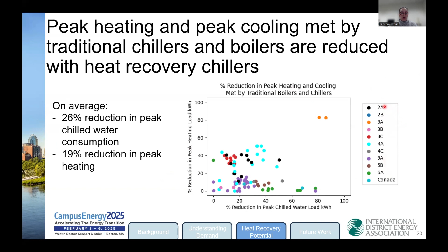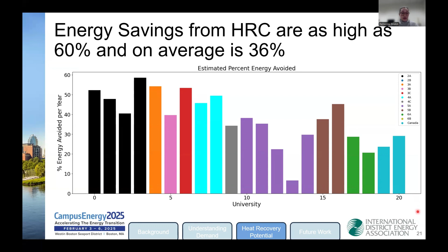Here we can see, with a back of the envelope calculation, what the energy savings from a heat recovery chiller might be for all the different universities. They are as high as 60% and on average about 36%. This is assuming back of the envelope calculations with efficiencies for traditional chillers as well as boilers, and then an electric heat recovery chiller. You can see that the energy savings are possible across the board with an average of 36%, which is actually quite significant. Now if we translate these to CO2 savings, we can see that installing a heat recovery chiller can reduce CO2 emissions on average 32%. And this is assuming average grid intensities for the US.